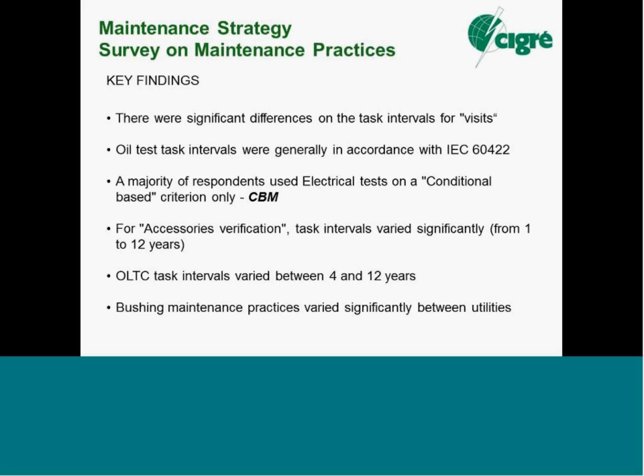Tap changers, well, they are the moving part in the transformer. There is wear and tear, but there's also electrical arcing, wear on the contacts on the diverter switch, the part of the switch that makes and breaks the load current. So they do deserve careful consideration on how frequently we should be testing, or do we rely on online monitoring on the tap changers? Any questions on that? No.